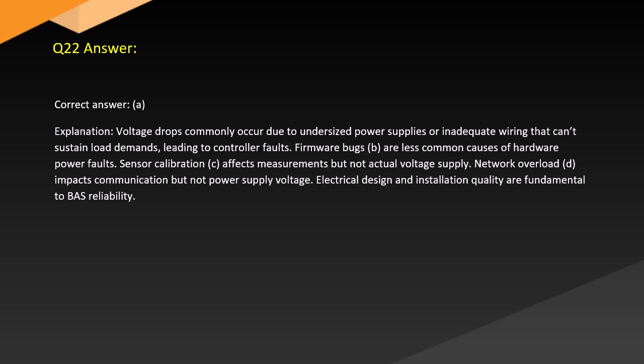Voltage drops commonly occur due to undersized power supplies or inadequate wiring that can't sustain load demands, leading to controller faults. Firmware bugs, B, are less common causes of hardware power faults. Sensor calibration, C, affects measurements but not actual voltage supply. Network overload, D, impacts communication but not power supply voltage. Electrical design and installation quality are fundamental to BAS reliability.